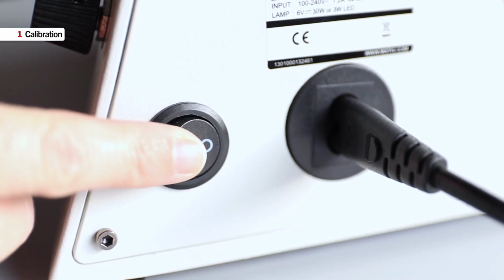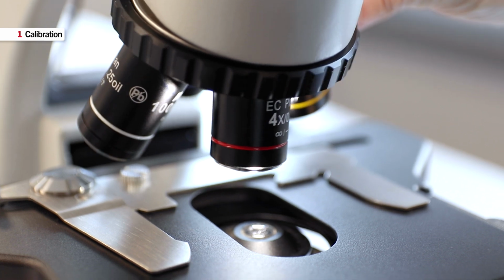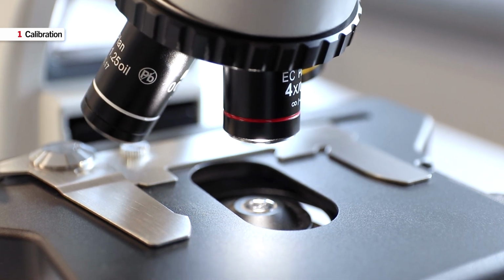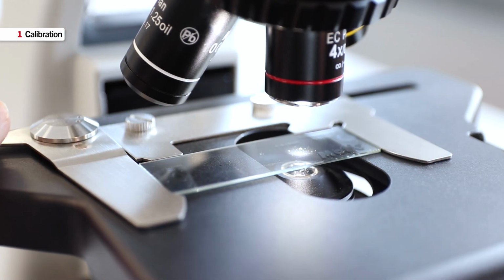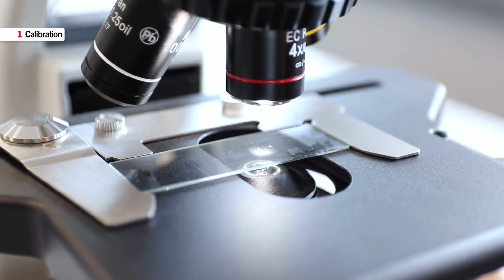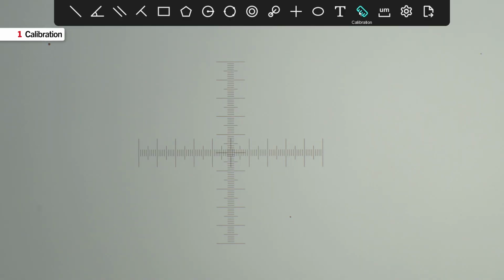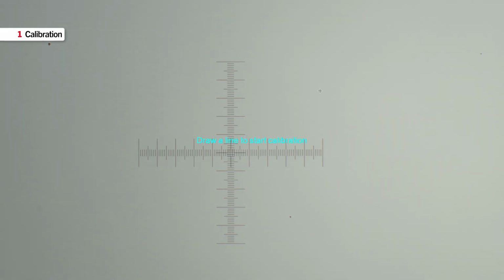Start by switching on your microscope and selecting the 4x objective. Place the calibration slide, locate the micrometer cross at the center, and bring it into focus. Click on the calibration icon on the toolbar at the top of the screen. Use the left mouse button to draw a horizontal line over the full length of the micrometer. We recommend selecting the longest distance possible for better accuracy.